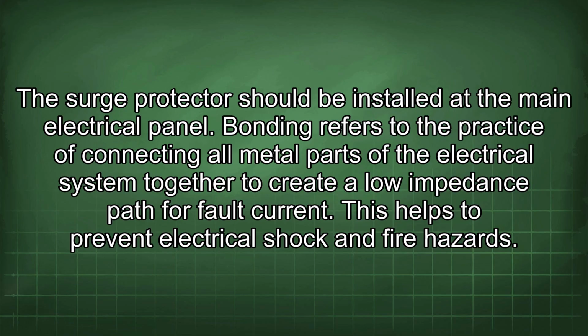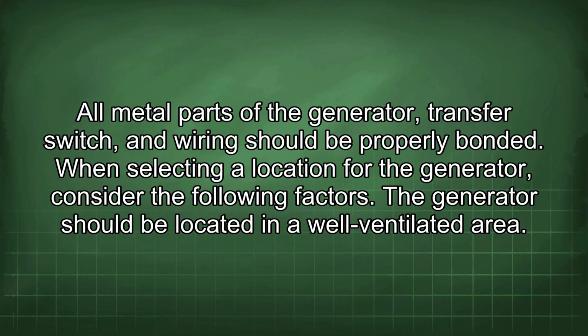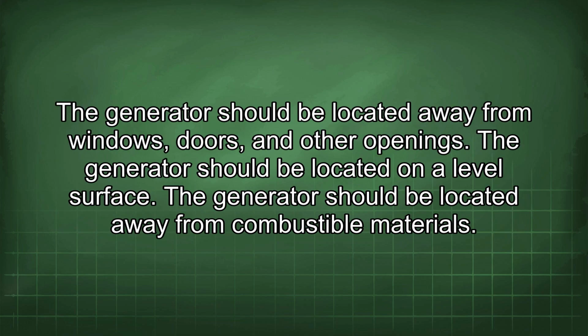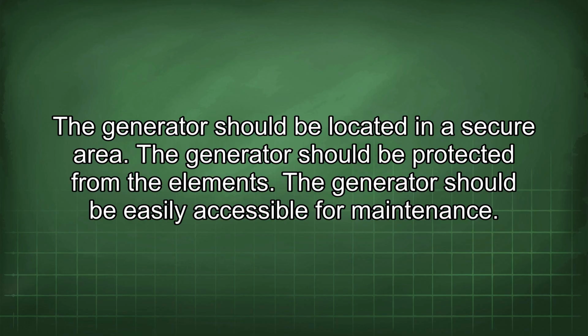Bonding refers to the practice of connecting all metal parts of the electrical system together to create a low impedance path for fault current. This helps to prevent electrical shock and fire hazards. All metal parts of the generator, transfer switch, and wiring should be properly bonded. When selecting a location for the generator, consider the following factors. The generator should be located in a well-ventilated area. The generator should be located away from windows, doors, and other openings. The generator should be located on a level surface. The generator should be located away from combustible materials. The generator should be located in a secure area. The generator should be protected from the elements. The generator should be easily accessible for maintenance.